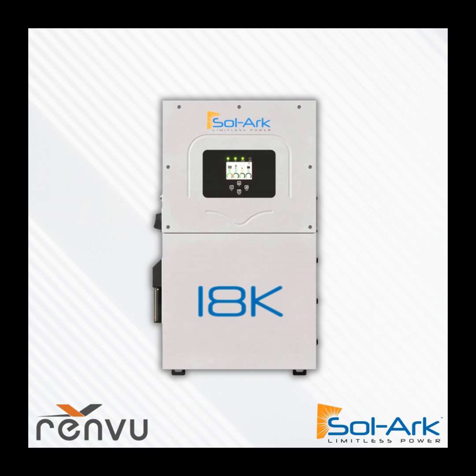Last but not least, on that gen port, if you're not doing an EV, a generator, or AC coupled solar, my favorite use of the gen port is simply to connect an additional subpanel and back up 2 panels rather than 1. You'd connect your main service panel to the load port, but let's say your home has an outdoor panel and an indoor panel and you want to back up both. You could land the outdoor panel on the gen port and the indoor panel on the load port and back up both for very easy wiring.